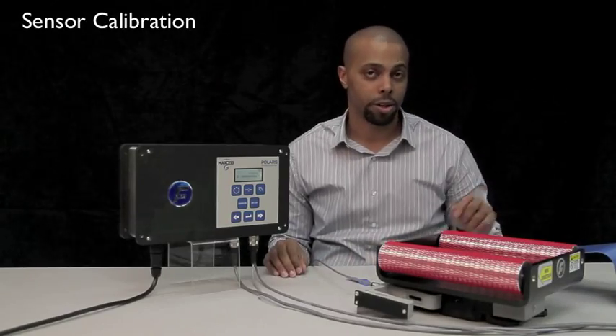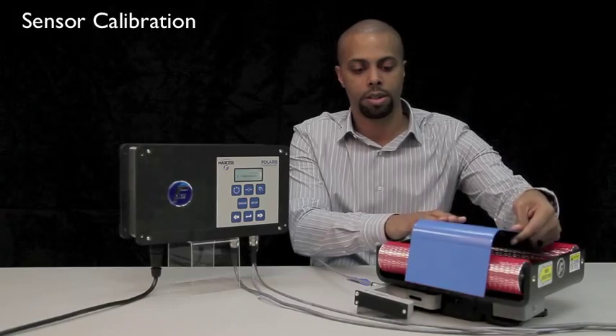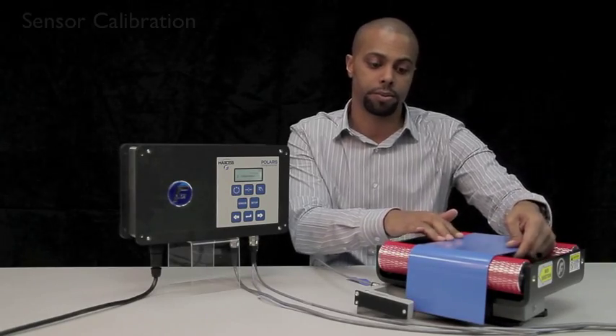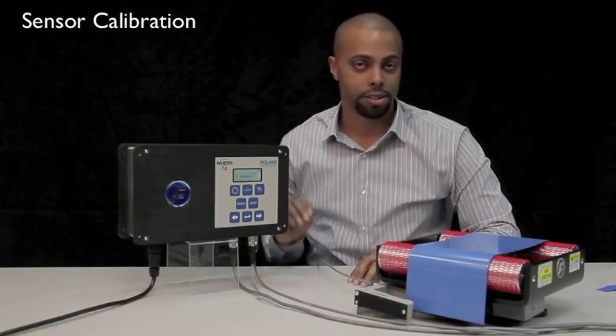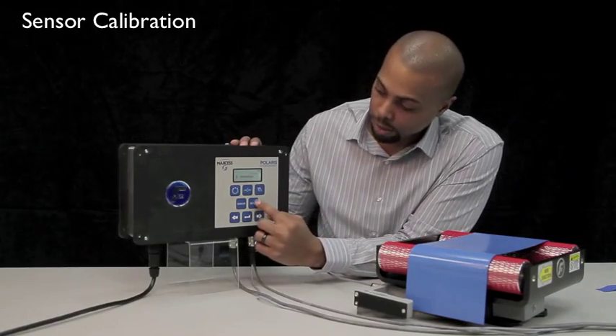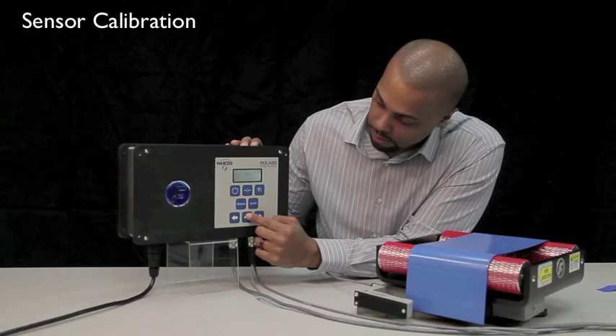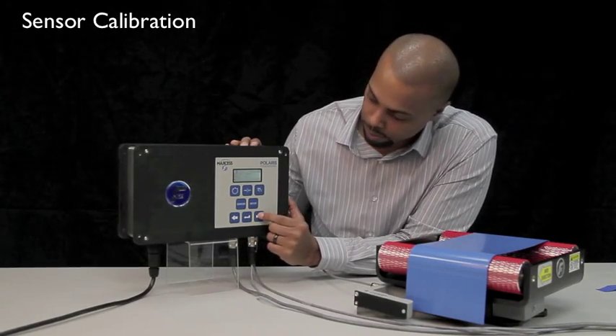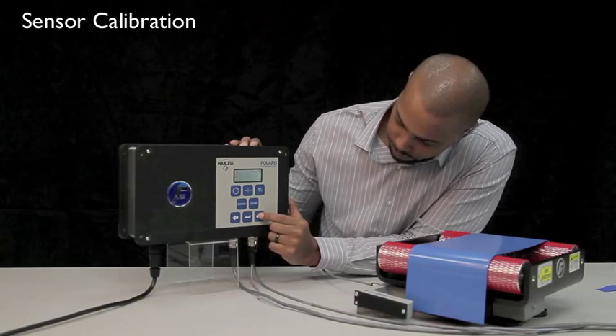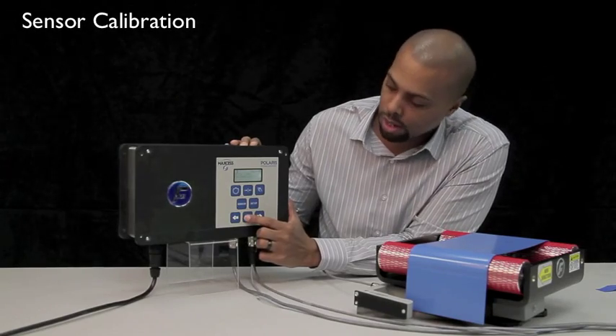We'll now calibrate our edge sensor using this blue metal strip as our material. To calibrate your edge sensor, first press the setup button and press enter to select your basic menus. Then press your right arrow until you see calibration and press enter to select it.